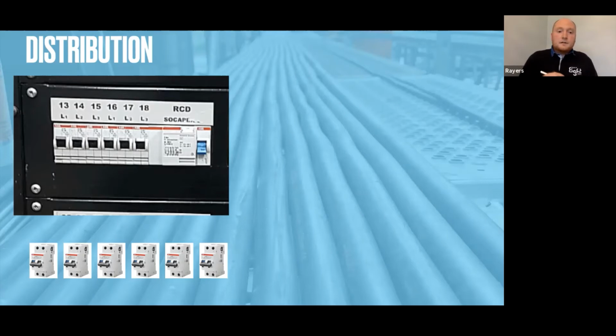The issue is that if you look at the circuits, there are a number of MCBs protecting you from overloading, but if any of those encounter a fault, you'd lose the whole board. That's what clients mean when they say everything goes off and they lose the whole system. So with 6 MCBs and 1 RCD, a fault means you lose the whole board.